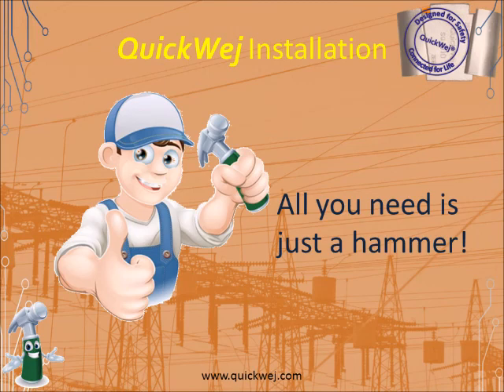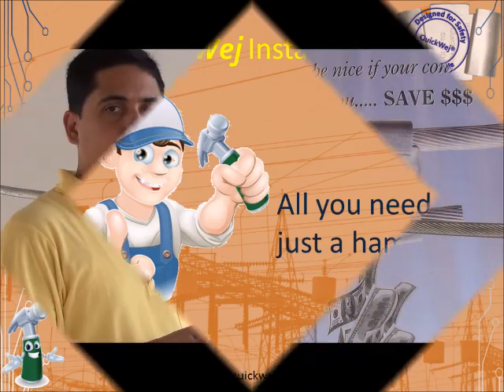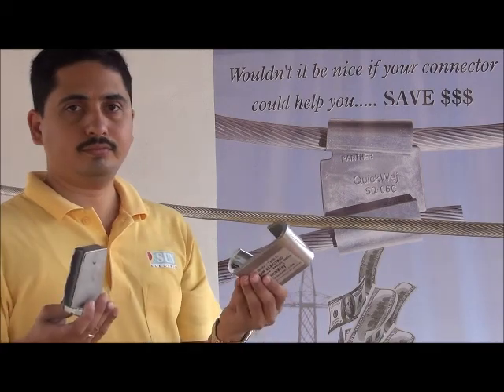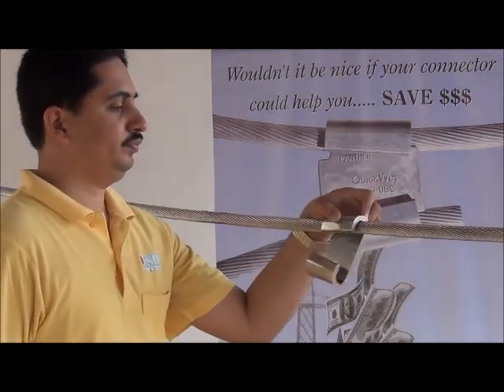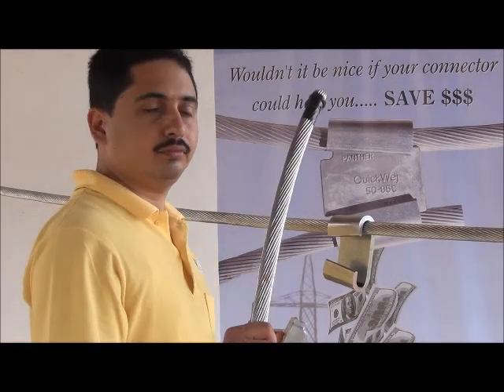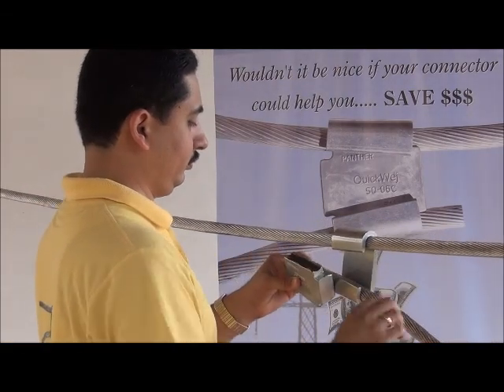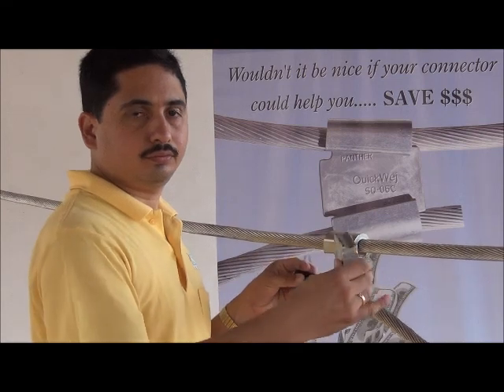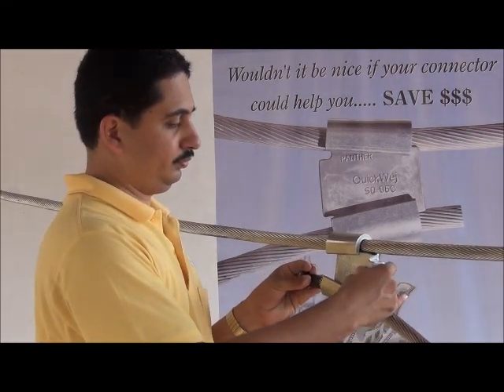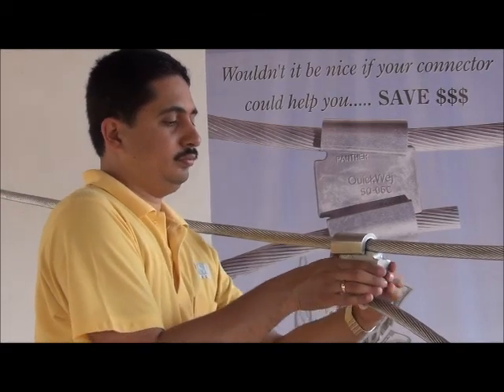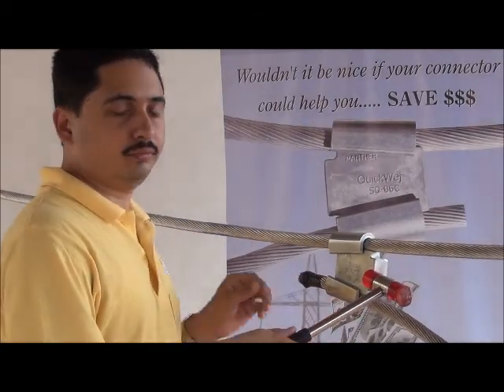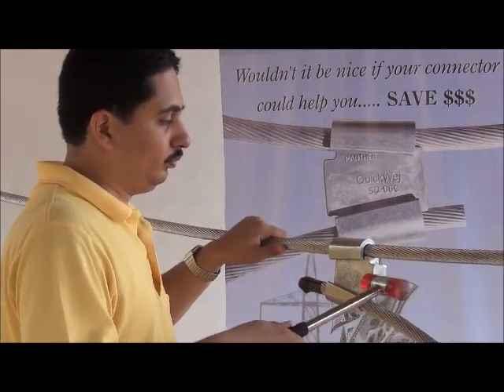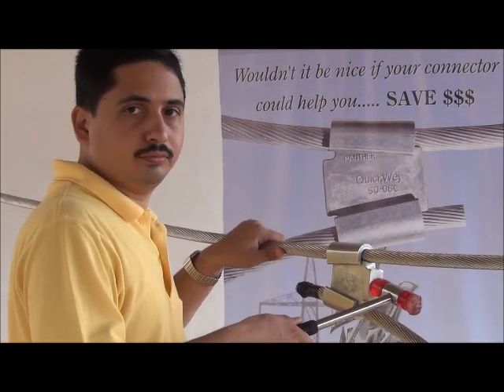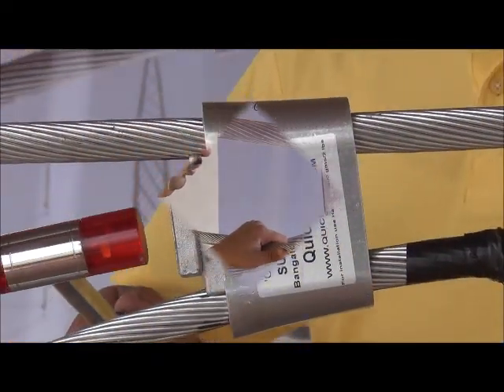Installation of QuickWej is quite simple. Unlike its counterparts, special tools and special skill are not necessary. A simple hammer does the job. Here, we will show you a short demonstration to take a tap using QuickWej. Suspend the C member on the run conductor or the main conductor, place the tap conductor in the lower groove, and insert the wedge and secure the wedge firmly by pushing it inside. Hammer the wedge until the stopper on the wedge flushes with the C member. Here, we have used a nylon hammer for the demonstration, but steel hammers can also be used.